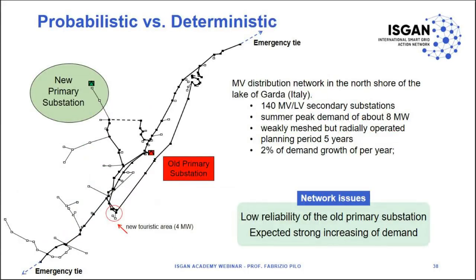Here's an example from a real case in Italy: a distribution network at the Lake of Garda. We have 140 medium voltage to low voltage secondary substations, demand of about 8 megawatts in this small area. The network is weakly meshed, though radially operated, the planning period is 5 years, and demand growth is 2% per year. The question is: do we need a new primary substation, meaning 150 kV to 15 kV and 20 kV?